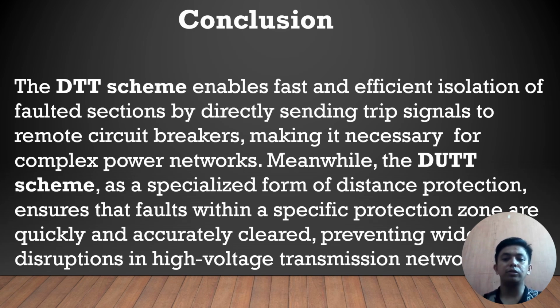So I also conclude that both direct transfer trip and direct underreaching transfer trip schemes are widely used in the protection of high voltage transmission lines, also in substations and power grids. Then the DTT is also commonly implemented in critical infrastructure such as interconnected substations and power plants, where rapid fault isolation is important to prevent cascading failures across the grid.